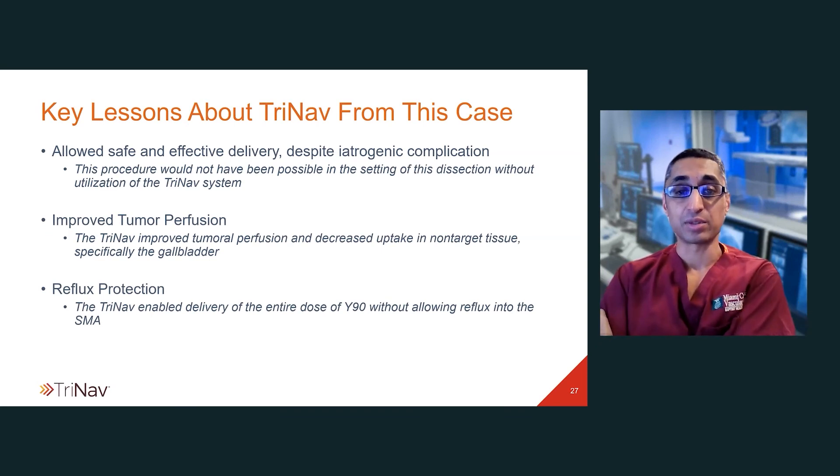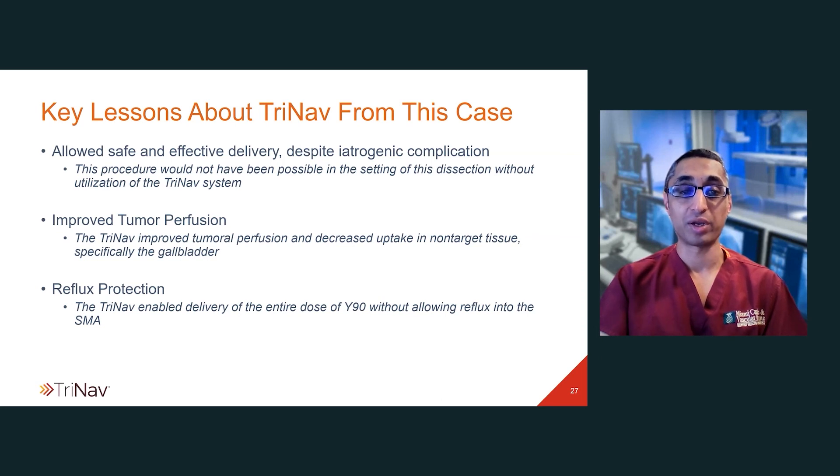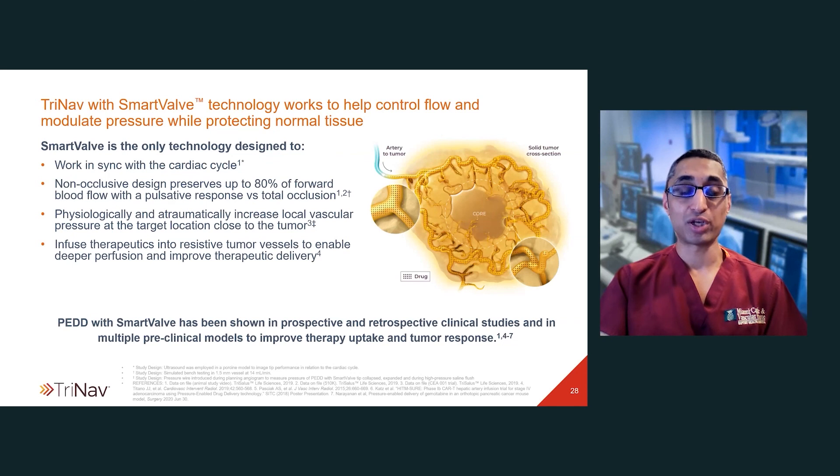The key lessons from TriNav in this case: First, it allowed for safe and effective delivery of Y90 despite the iatrogenic SMA dissection, and this procedure really would not have been possible without the device. Second, there was improved tumoral perfusion — the TriNav allowed improved perfusion of the tumor and decreased uptake to non-target tissue, specifically the gallbladder. Finally, the TriNav enabled delivery of the entire Y90 dose without allowing reflux into the SMA, which would have been catastrophic. This TriNav system with pressure-enabled drug delivery and the SmartValve has been shown in multiple prospective and retrospective clinical studies, as well as preclinical models, to improve therapy uptake, tumor response, and prevent reflux.